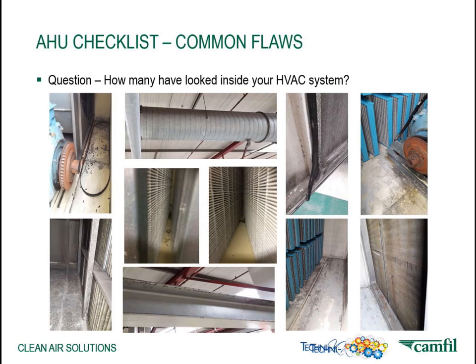When you look at an air handling unit, there are several items that should be inspected, confirmed and maintained. As we can see from the pictures in this slide, fan belts and bearings, droplet separators, and doors should all be inspected to ensure that they are in working order and do not pose any risk to a facility. We can see the effects of poorly maintained air handling units in some of these pictures, from what we can see on the gaskets, especially in the picture on the top right-hand side. Gaskets are not supple and they're in poor quality. Air, in effect, bypasses and does not get filtered. High moisture can cause corroding and exacerbate issues within an air handling unit. Dust buildup also happens and can be seen in the pictures within the production areas. And these are some of the negative impacts of poor maintenance within an air handling unit.